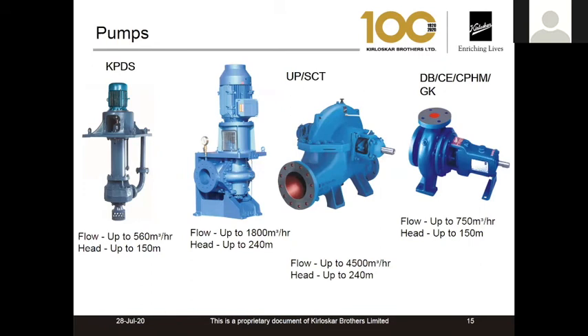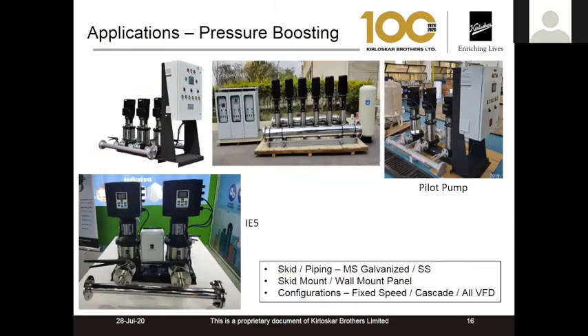So I'll just go to the various designs or themes. You can see the various design options. Here you can see vertical inline pumps and various designs of the systems. You can see the panel is mounted on the skid itself, or a separate panel because it's a big system. Then you can also see the pilot pump system, where one pump is smaller than the other two pumps.